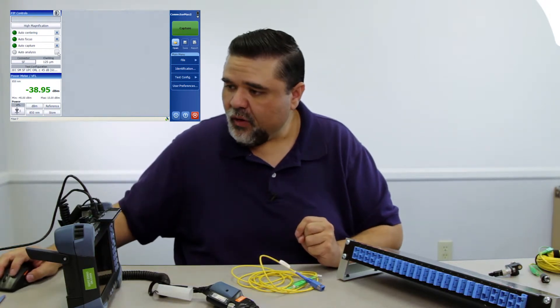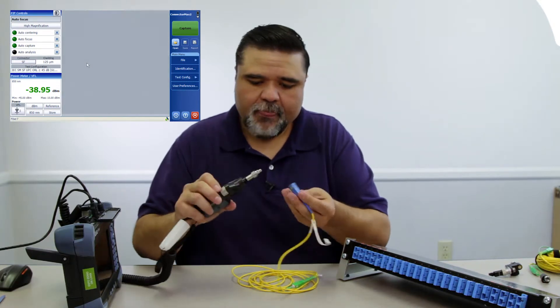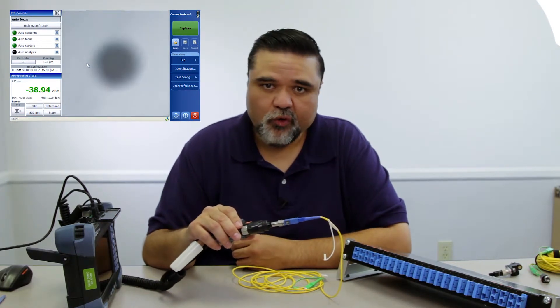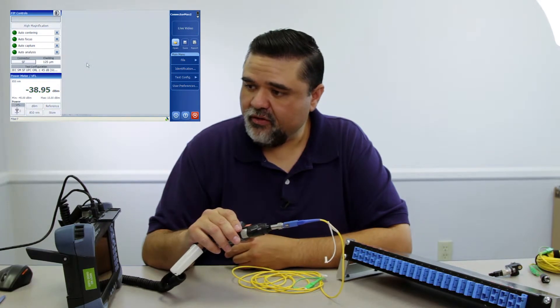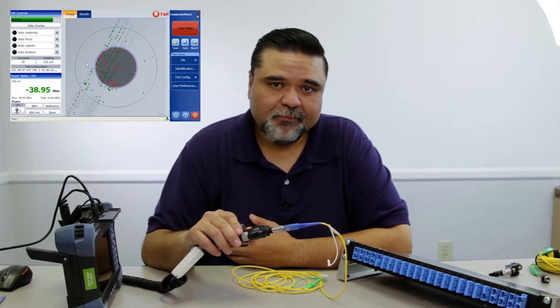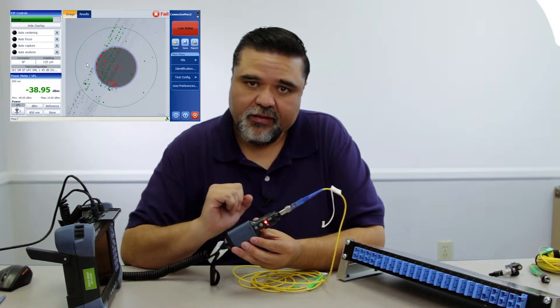If I turn on auto capture and auto analysis on this unit, you'll get to see the whole test suite. There are little motors in here you can feel moving around while holding the probe. It'll auto-center, auto-focus, then auto-capture, and then do the auto analysis. And there's the red LED — that is a fail.